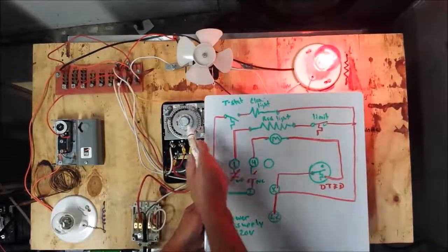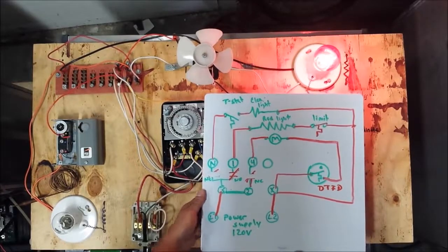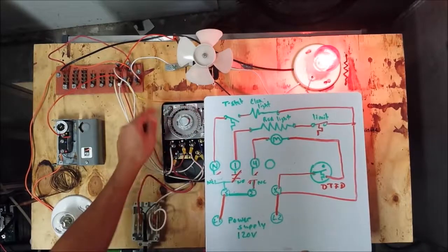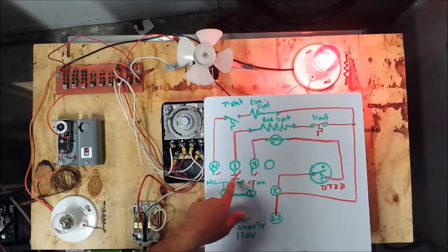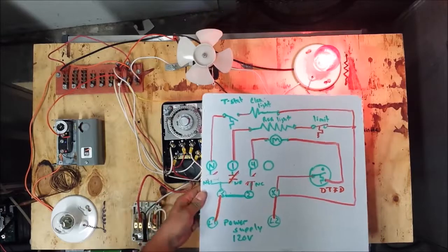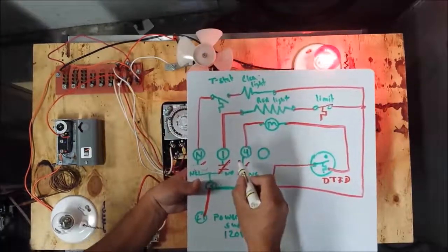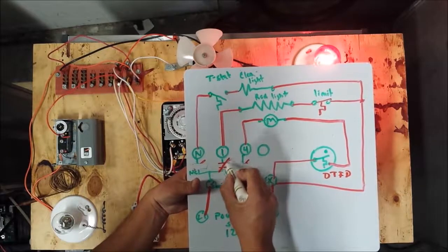Okay? Now, one thing I may have mentioned to you guys earlier on, once again, is behind the scenes here we have a solenoid coil behind it. If it is energized, it's going to kick this thing out of defrost and open our normally open switch and reclose our normally closed switches. Okay? Now, in a diagram, it's basically getting power behind the clock from our normally open switch.